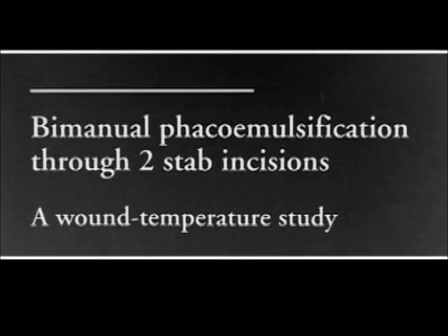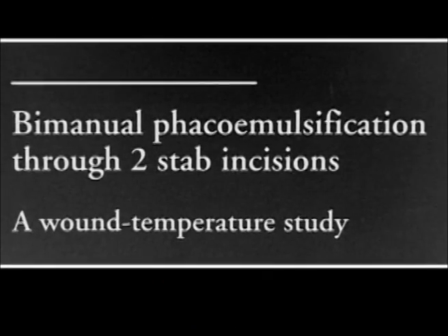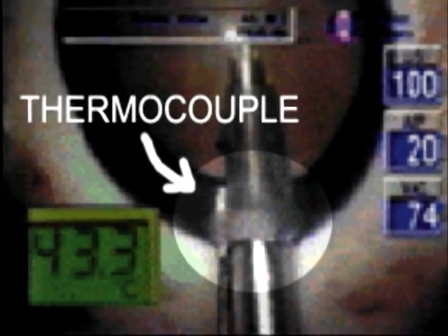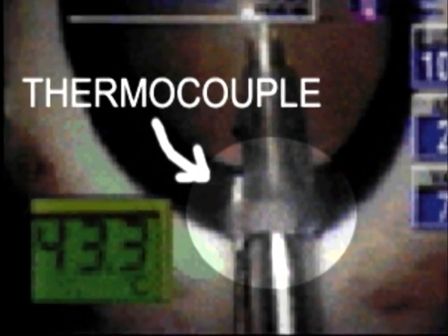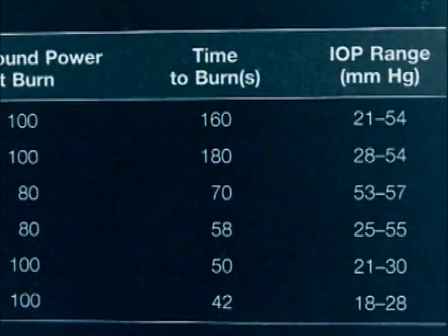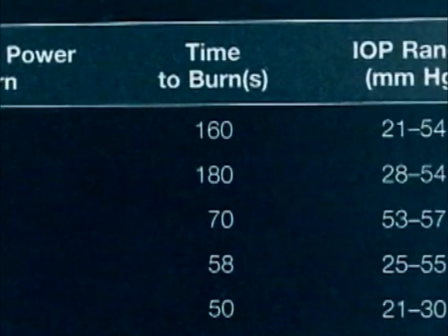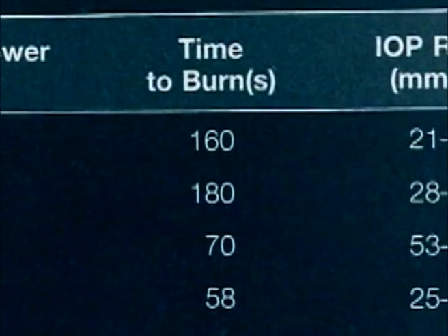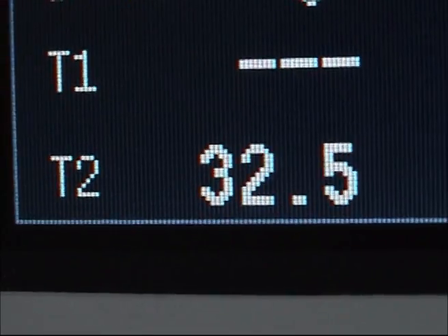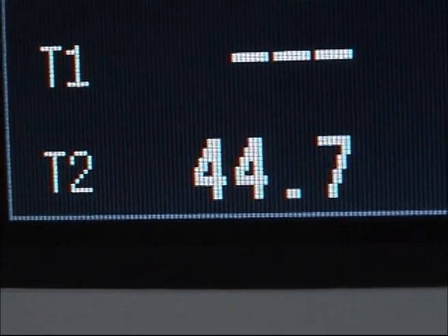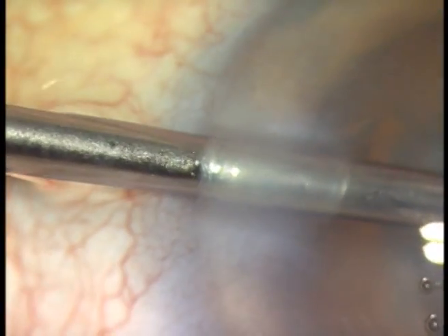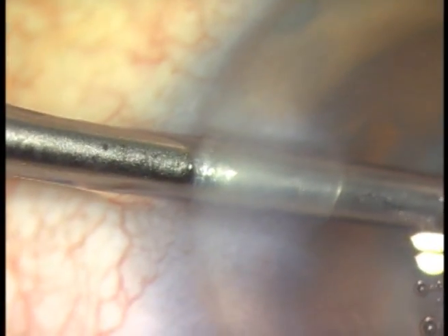Unfortunately, most studies pointing in this direction have used thermocouples inserted somewhere within the incision. These studies report dangerous temperature rises under worst-scenario conditions occurring after several seconds, even minutes, of ultrasound. No consideration is made in these studies regarding incision distortion, altering flow, and friction areas by the placement of the sensor element.